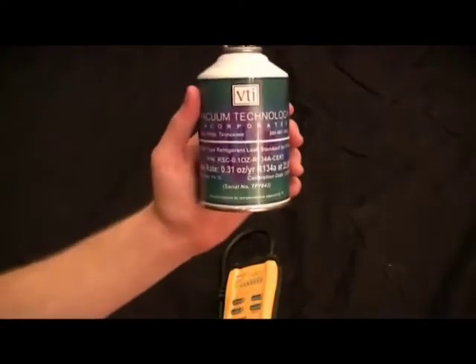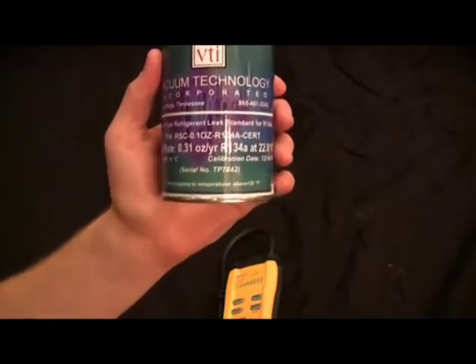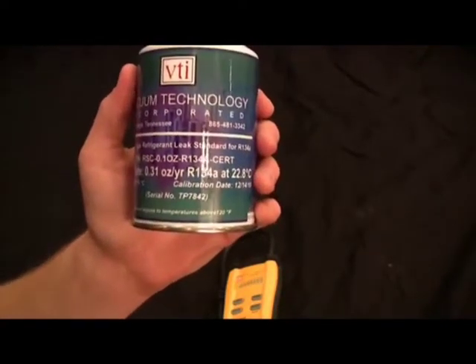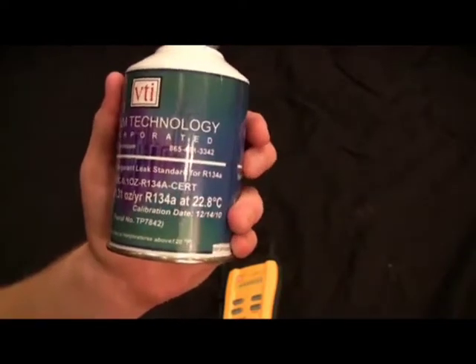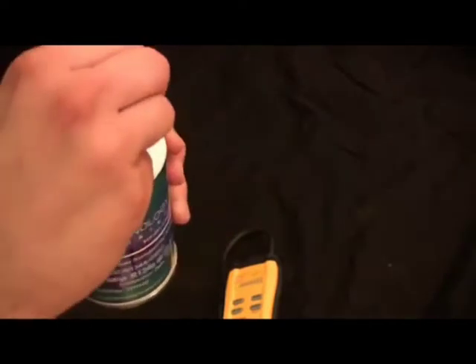Now the SRL-2, what it first stabilizes to is the level of refrigerant inside this room or inside the environment that it's in. Now if we were in a contaminated area, it would stabilize to that level of refrigerant. Now because it's always looking for the highest level of refrigerant, you do have to keep it moving when you're sensing leaks.